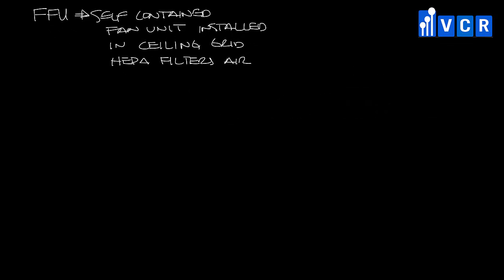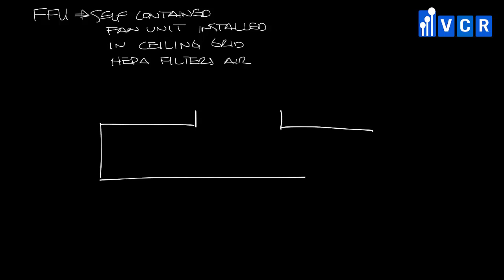Let me make a little room and show you what one looks like. Fan filter units basically look like this. They fit in a 2x2 ceiling grid. They may have an inlet that's ducted to supply air, but most of the time they pull air from an open plenum.